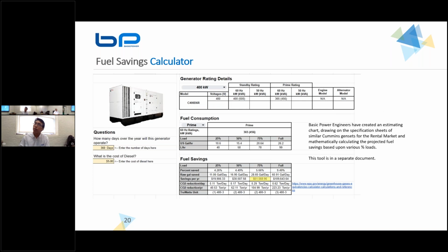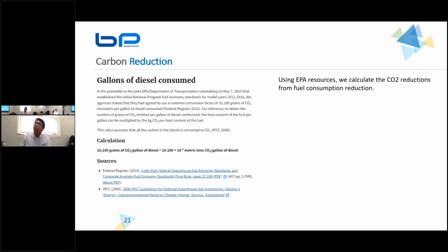We actually have a fuel savings calculator, and this calculator depends on the make and model of the generators itself. Based on the values that we can find on a spec sheet, we can use what we found in our white paper to calculate what savings we can see, like how many gallons per day if you operate for 360 days a year, right? Depending on your diesel costs, we can calculate a financial savings and benefit from having this correction in the system. All these calculations were made using the EPA resource. There's a good tool that we used, which allows us to calculate the carbon emissions based off the gallons of diesel consumed. So we can directly correlate the amount of CO2 reduction based off how many gallons of diesel we save.